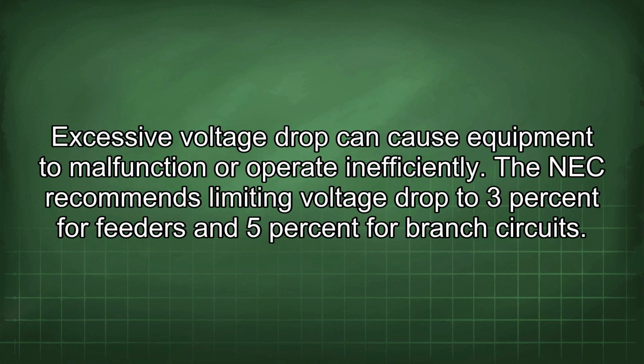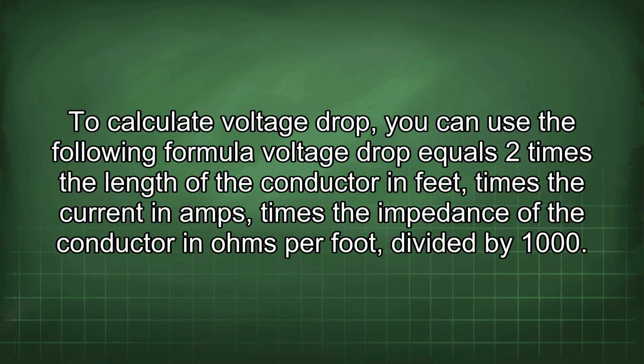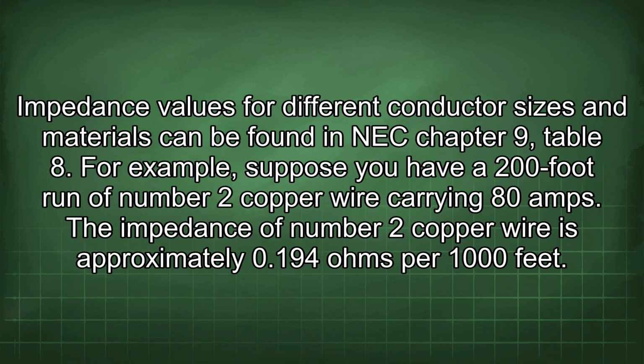Excessive voltage drop can cause equipment to malfunction or operate inefficiently. The NEC recommends limiting voltage drop to 3% for feeders and 5% for branch circuits. To calculate voltage drop, you can use the following formula: voltage drop equals 2 times the length of the conductor in feet times the current in amps times the impedance of the conductor in ohms per foot divided by 1000. Impedance values for different conductor sizes and materials can be found in NEC Chapter 9, Table 8.